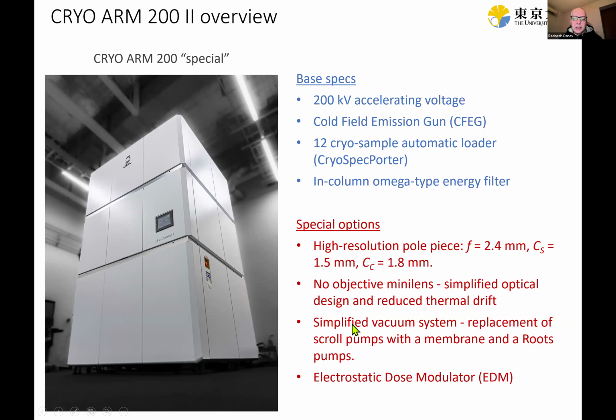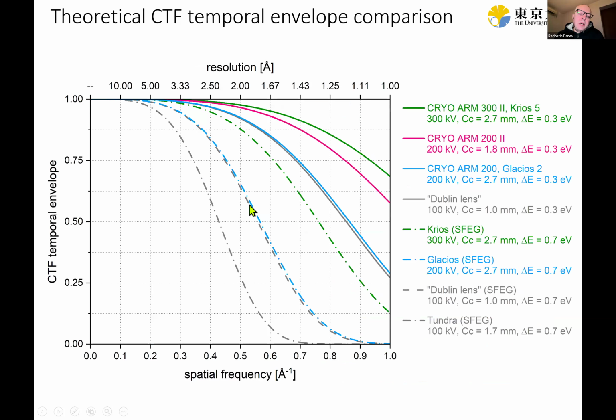And by removing this lens, they optimized the overall performance. Also, the vacuum system was simplified, so smaller and quieter pumps, requiring less service. And finally, the electrostatic dose modulator, which is a very fast electrostatic shutter, which can be used both as an electrostatic shutter and as a beam intensity modulator by applying a modulating frequency which is much higher than the frame rate of the detector. So the basic optical performance of the microscope is determined by the contrast transfer function temporal coherence envelope.